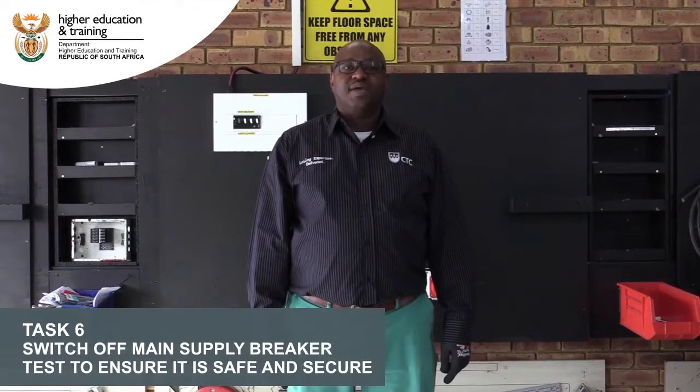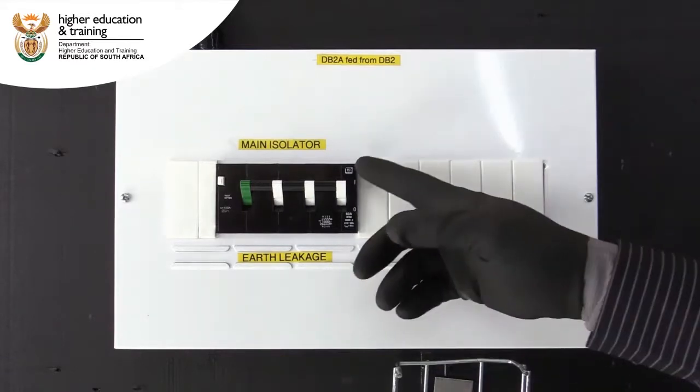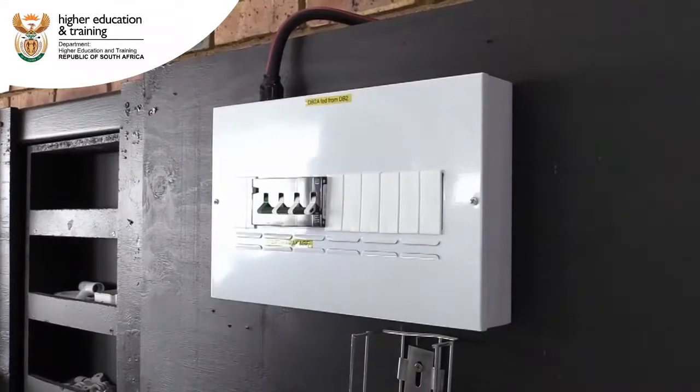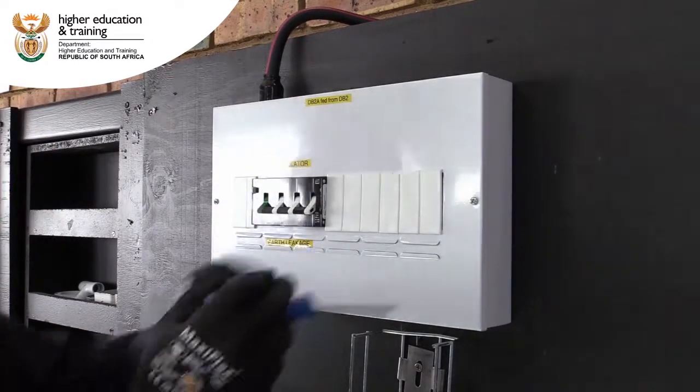We're going to switch off the main supply breaker and test whether there's no voltage. We need to identify the main isolator and switch it off. As the main isolator is off, we will have to ensure that there's no power by using a multimeter and test for zero voltage. We will unscrew the cover using a flathead screwdriver.